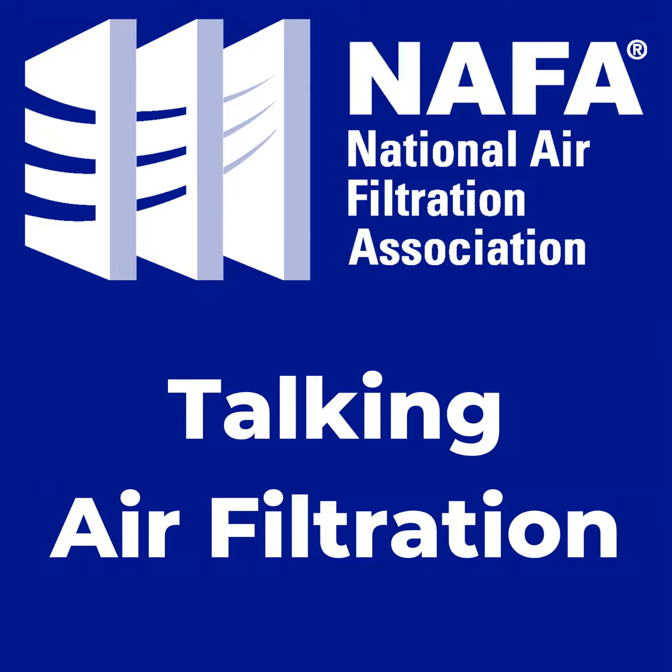So an easy one, being with AAF, we talk about the PTFE HEPA filter media. This is a nanofiber application where you can see a really big difference in how filters perform with bigger fibers versus the smaller nanofibers. You can see here on the left side, the pictures are the microglass, like a traditional HEPA filter media, and on the right side, you see the ePTFE type HEPA filter media. The scale isn't the same on those top pictures. Obviously, I've got a really good zoomed in picture so you can see how those nanofibers impact the structure and how it looks more closely, because if I had it zoomed out more, you wouldn't be able to see that structure as well.